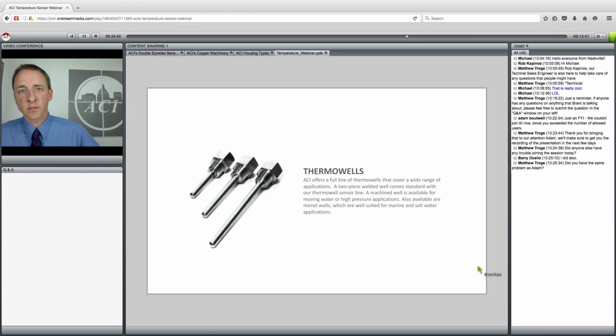However, that's changing, and sometime in the very near future we're going to move to an all one-piece well, like this one, which we call a machined well. It's cut out of a solid piece of stainless steel, and that's going to be our default. Very soon you'll be getting information on when that changeover is happening. Right now we're just building up our inventory in order to make that change. The machined wells are more sturdy, being one-piece, and suitable for high flow rates and very high pressures.